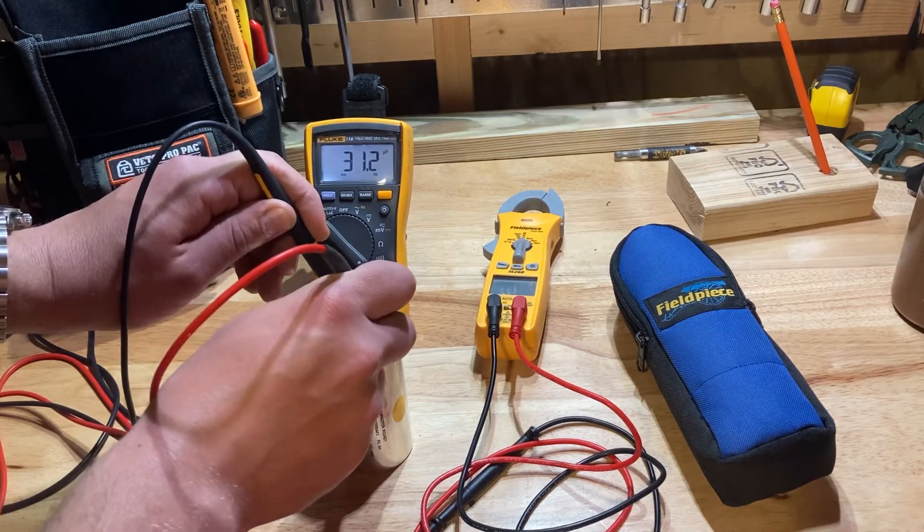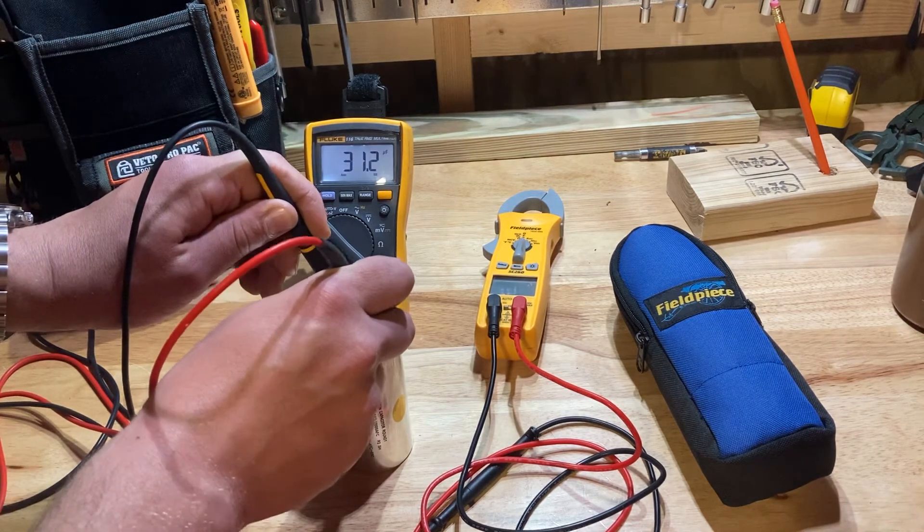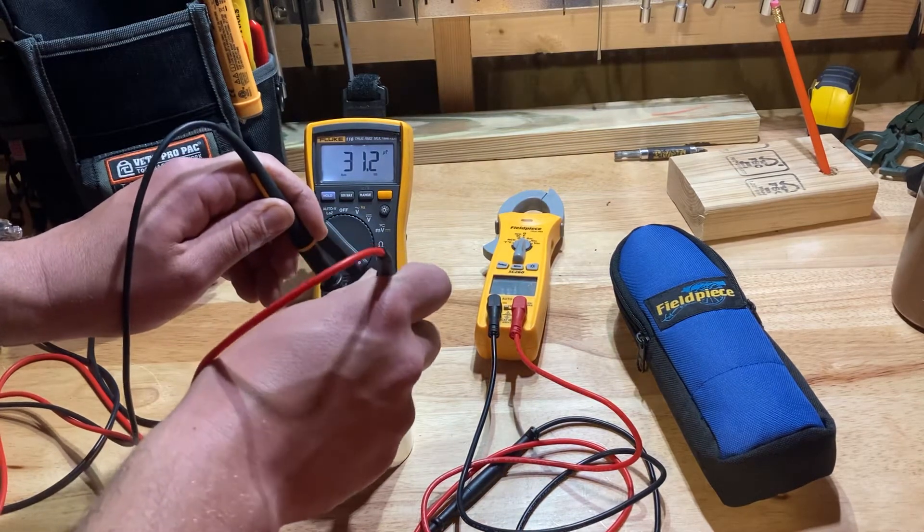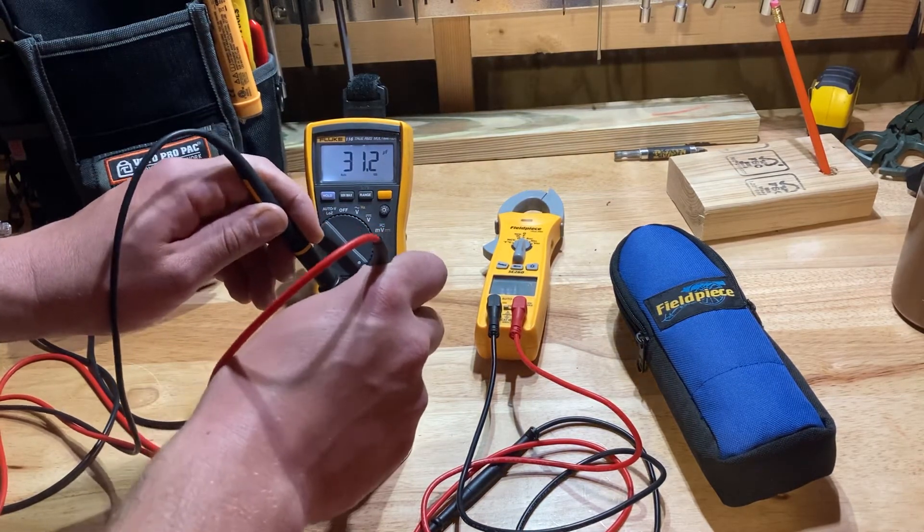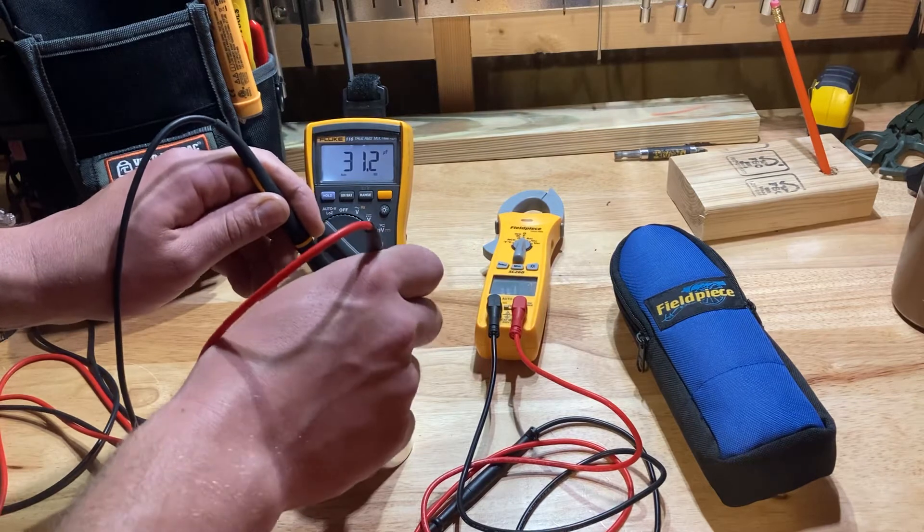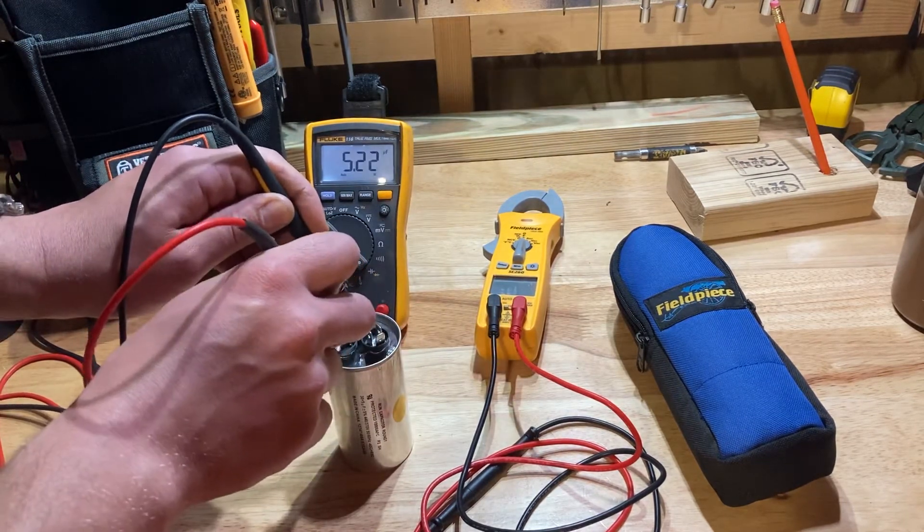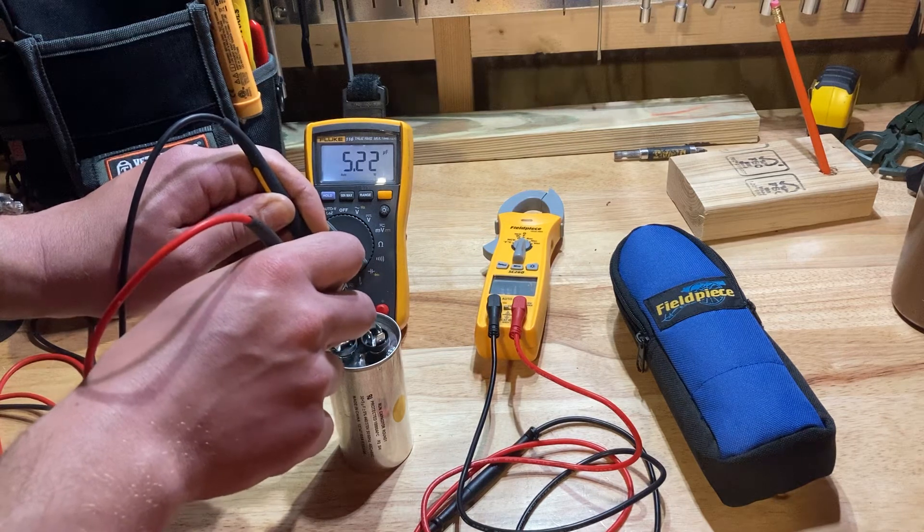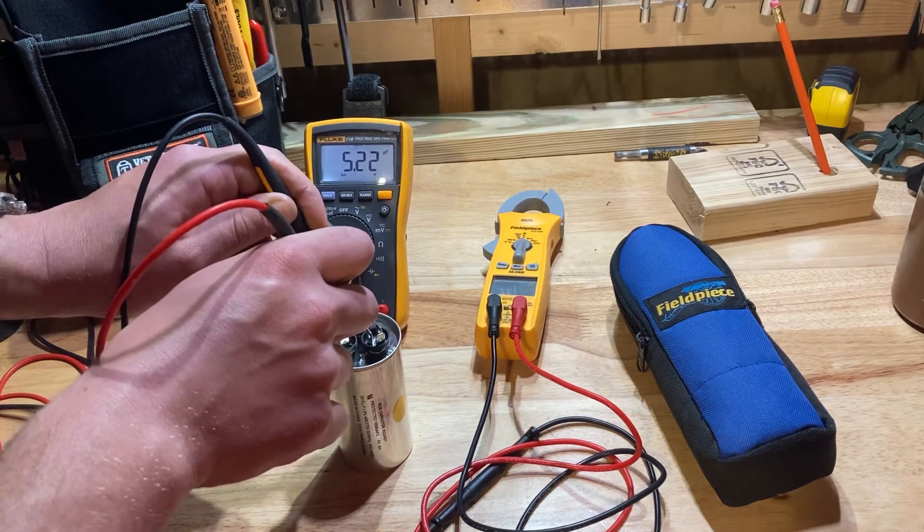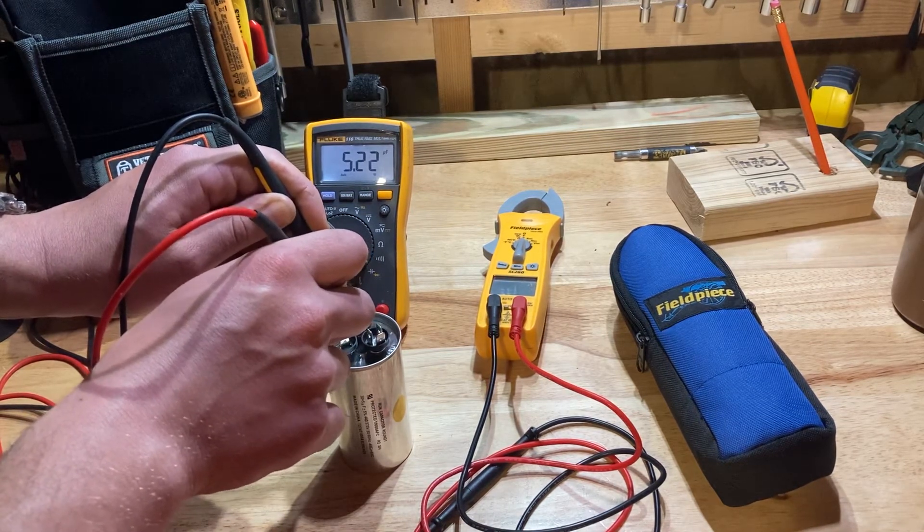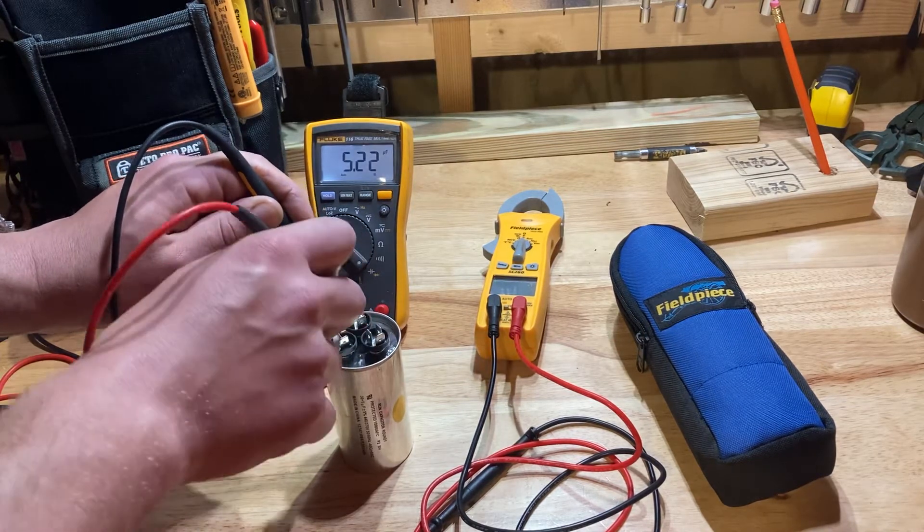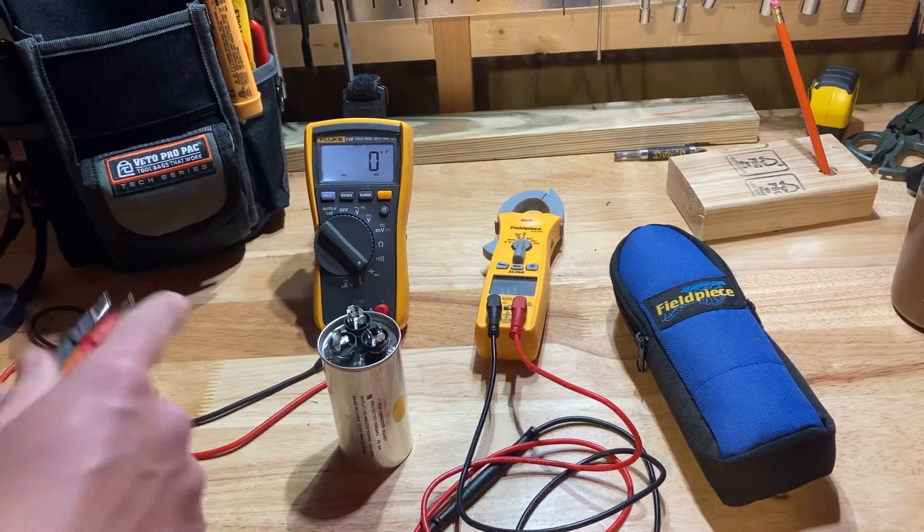You see how fast and non-glitchy that went? 31.2. So this is good. This is a new capacitor, so it should be good. Then we're going to go common to fan. 5.22. So we're good. And the numbers don't jump around. Everything is right on the money. It never changes. It's just perfect. I mean, it just tells you exactly what you want it to tell you.